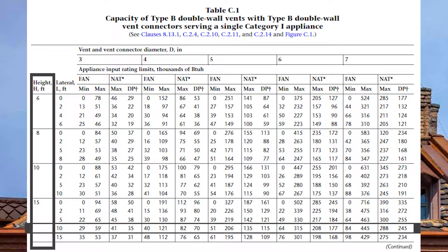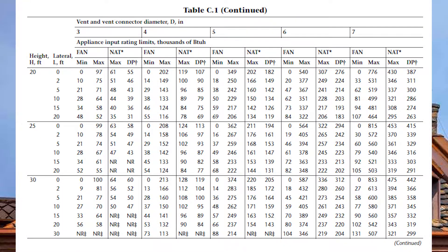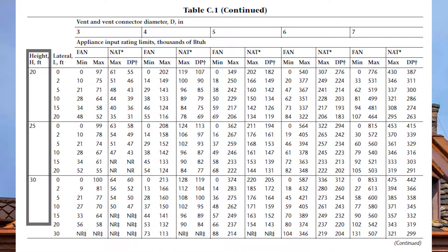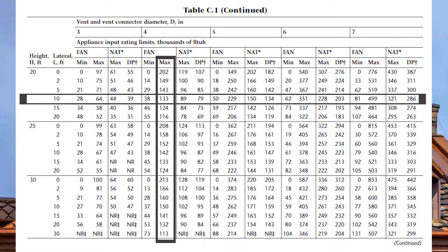3 inches is too small. 4 inches is good to 121,000 BTUs — that's close, so we write that down. Now we come down to the 20-foot vent height and go across on the 10-foot lateral. I need to go to the 4-inch section to compare apples to apples. Looking at the fan max, it's 133,000 BTUs — write that down because now we need to interpolate.